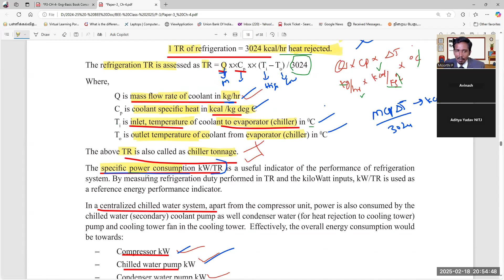Specific power consumption equals kilowatt. Always remember, power always comes top side, don't forget this, okay? Kilowatt divided by TR. What's the shortcut? Input divided by output, opposite for efficiency, always remember input divided by output. This is specific power consumption: kilowatt divided by TR, very important, 1 mark.